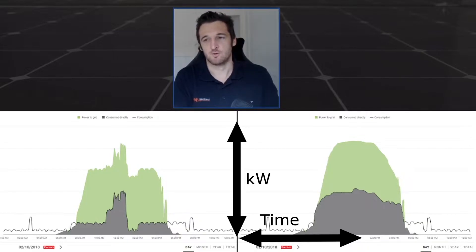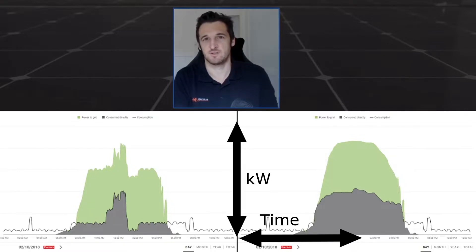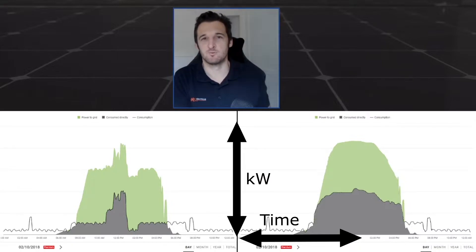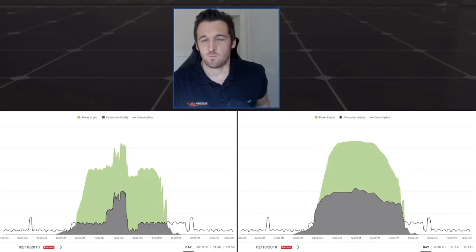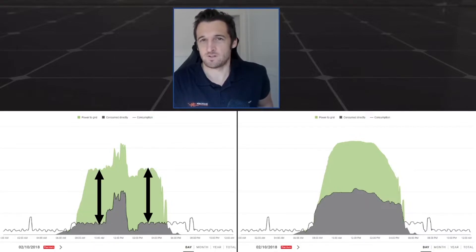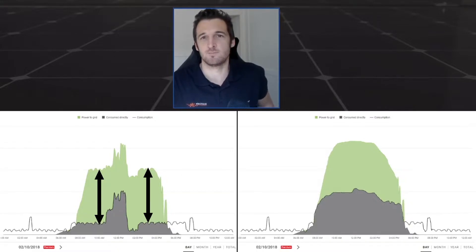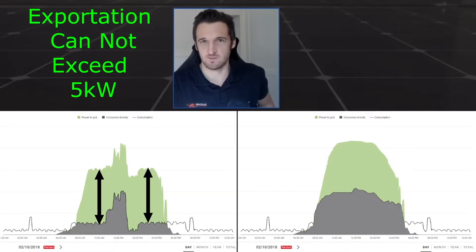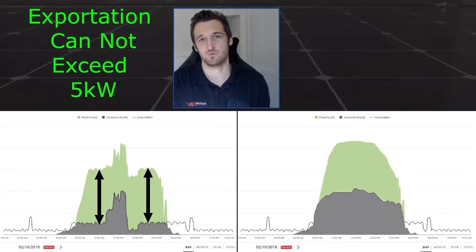For the color codes, the green portion is the amount being sent to the grid for a feed-in credit, and the gray filled-in section is what's being used by the household directly. You'll also notice an unfilled gray section which is being used by the household but bought from the grid because solar at these hours isn't functioning — it's night time. What export limiting is most concerned with is this green portion, the power to the grid. At any one time this amount can't exceed a certain amount. Referring back to the Energex guidelines, the most common amount is five kilowatts, meaning this green section can never be higher than five kilowatts even if your system wants to produce more.